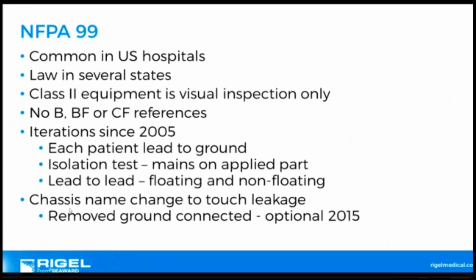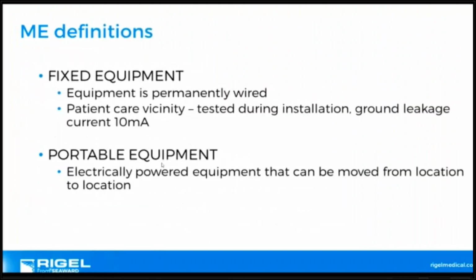Chassis and some of the new terminologies with enclosure, touch / chassis, it's now in line with international standards, and we call it touch leakage. And they removed some ground connections as part of the testing, with them being optional in 2015. So it has had iterations over the years. Fixed equipment has its own definition in that fixed equipment is permanently wired. The patient care isn't within the vicinity of this device, and we only do ground leakage at 10 milliamps.